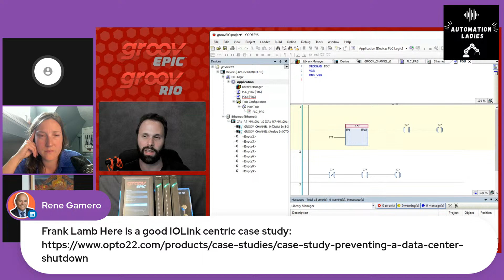It's a facility where they had to completely re-outfit with essentially a new chilled water system, but they couldn't run wires through the building because of building code - it was an old concrete building and you couldn't drill anything into it. So they used IO Link sensors on each floor, and with an Ethernet cable - since they already had some Ethernet capability through the floors - they used all these IO Link sensors along with the GRV-EPIC.